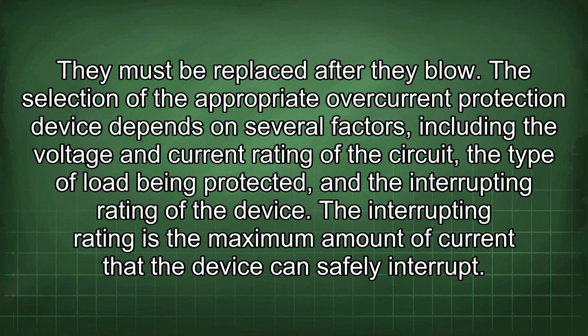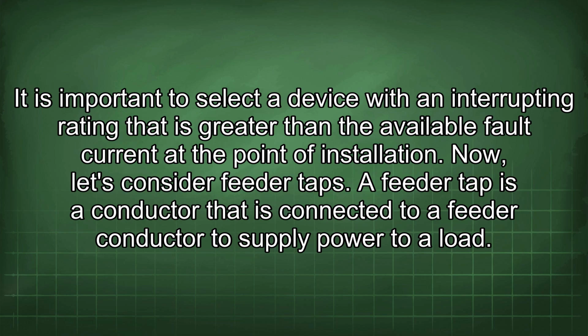The selection of the appropriate overcurrent protection device depends on several factors, including the voltage and current rating of the circuit, the type of load being protected, and the interrupting rating of the device. The interrupting rating is the maximum amount of current that the device can safely interrupt. It is important to select a device with an interrupting rating that is greater than the available fault current at the point of installation. Now let's consider feeder taps.